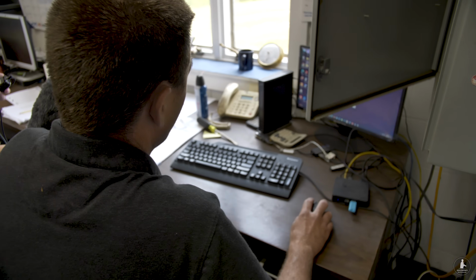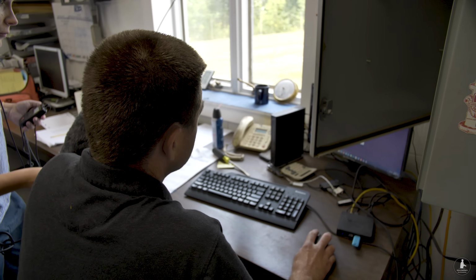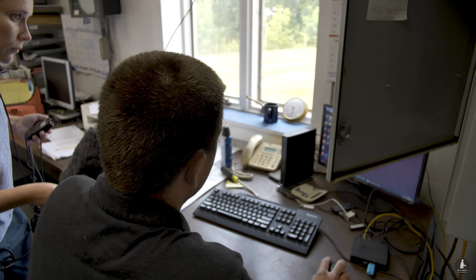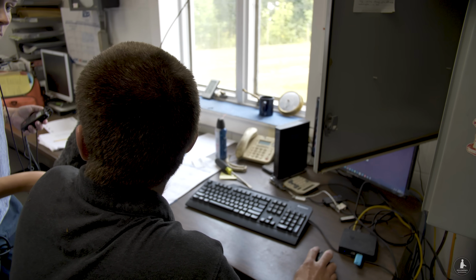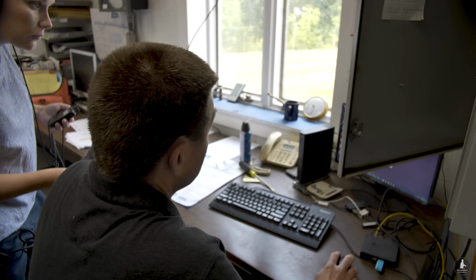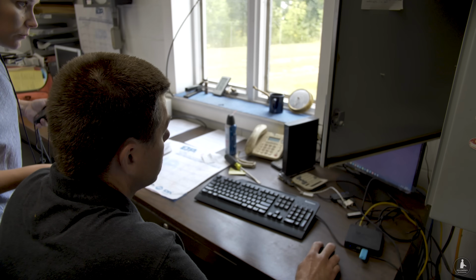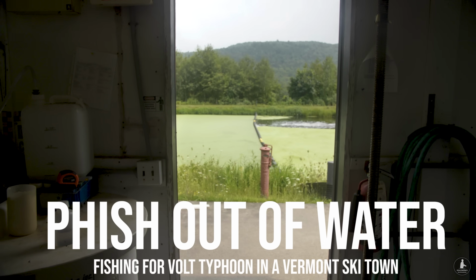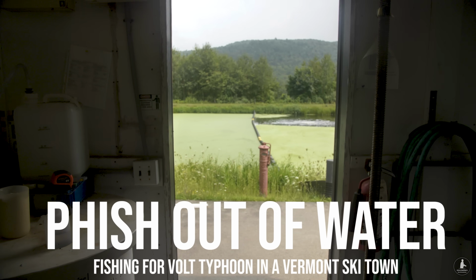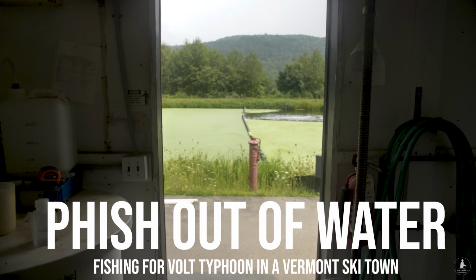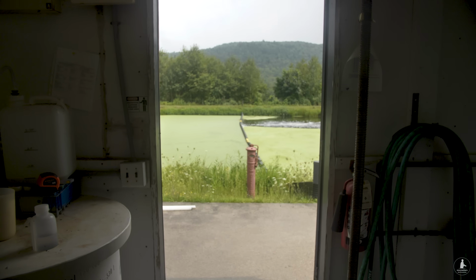we can have no more than 0.1 milligrams per liter of chlorine when it enters the river. So we have to monitor that. So these numbers you're seeing are real-time numbers, these percentages of the pump. So we're on 350 now, so let's max it out at 450.